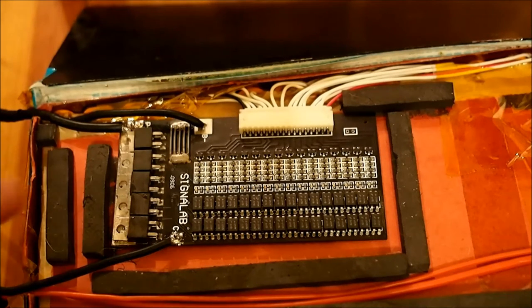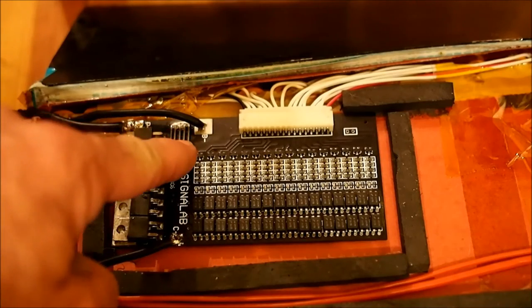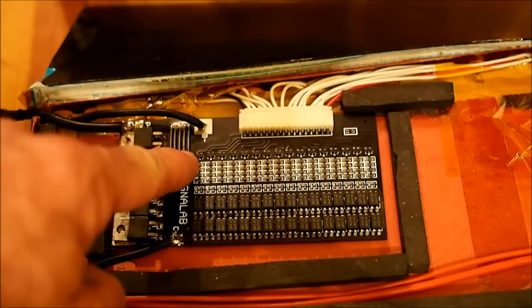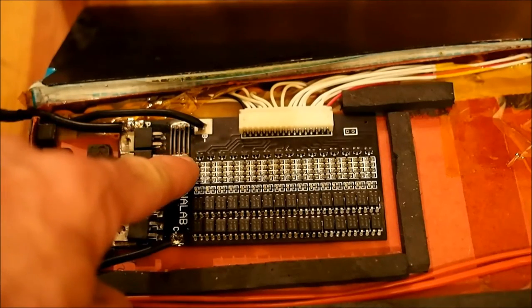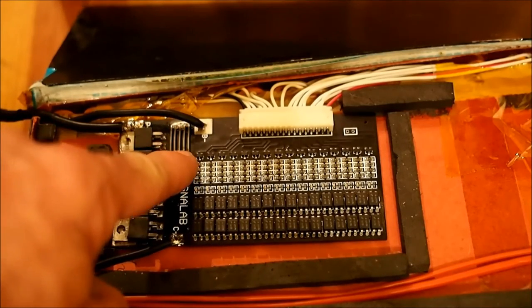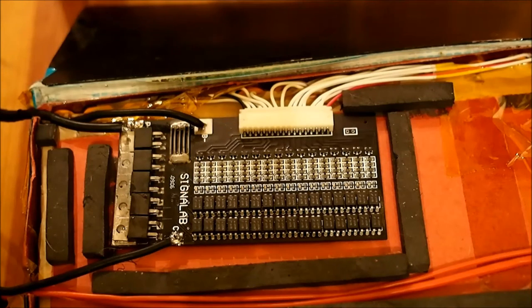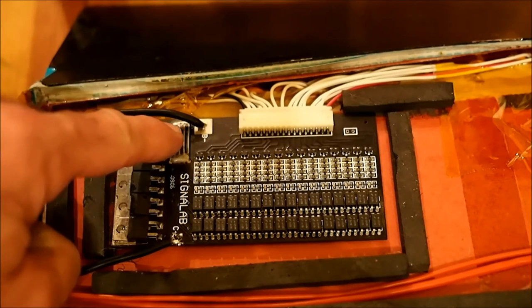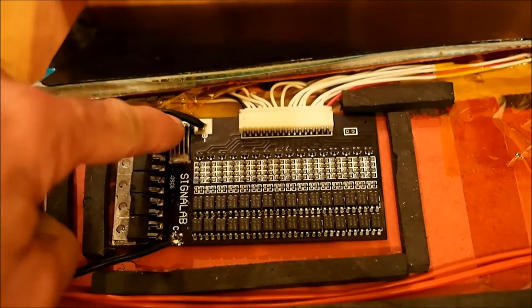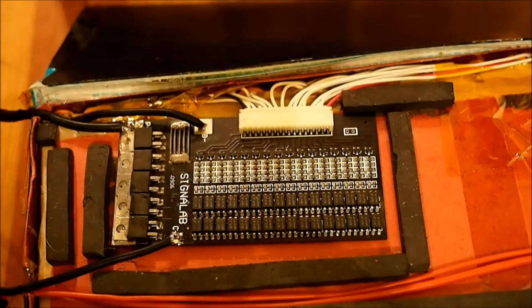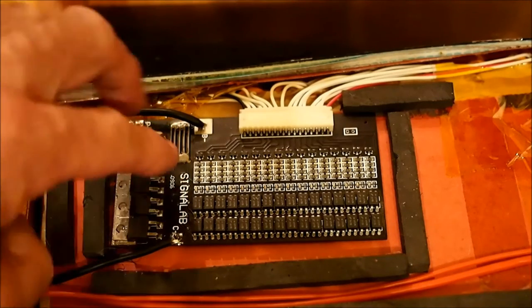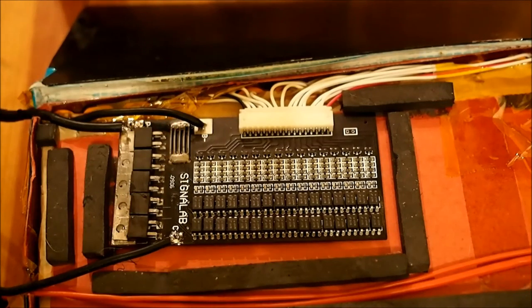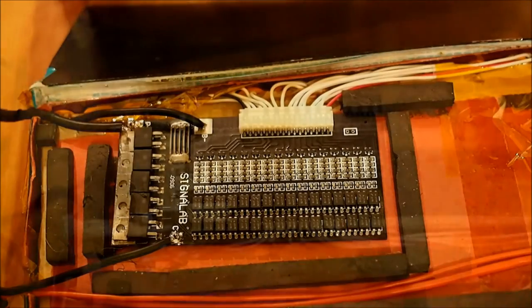So anyway, next thing we're going to look at, these vertical wires here are basically one big load sensing resistor, and its only job is to provide a little bit of resistance between there and there. If the voltage between those two spots gets too high, it'll disconnect the discharge circuit.